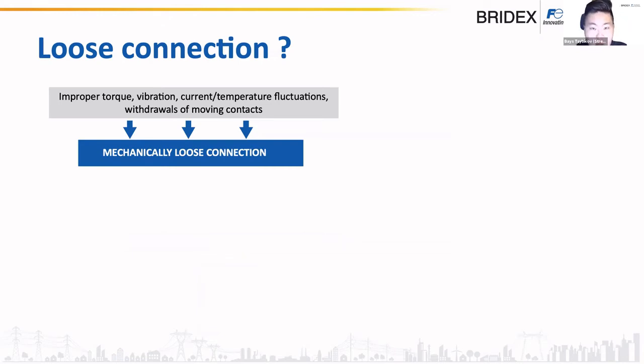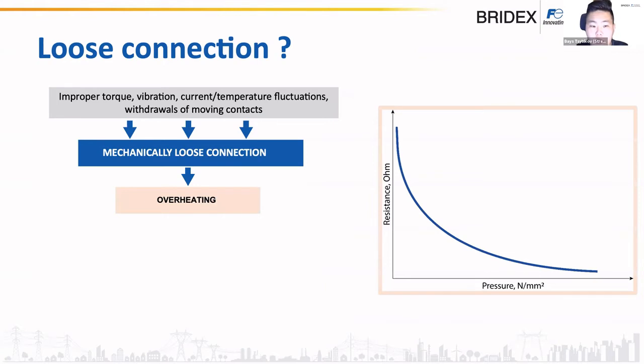About the loose connection, which is the most common thing in the electrical panel: how does it happen and what can it lead to? Every loose connection starts with a poor mechanical connection for different reasons. You can see them here: improper torque during assembly, or vibration if you have motors in the facilities, or current and temperature fluctuations expanding and squeezing the contact. And for moving contacts, it is the number of withdrawals. Let's say the circuit breaker, you put it in and out, and after 100 times, this connection gets loosened. So these reasons lead to a mechanically loose connection, and this mechanically loose connection leads to overheating.